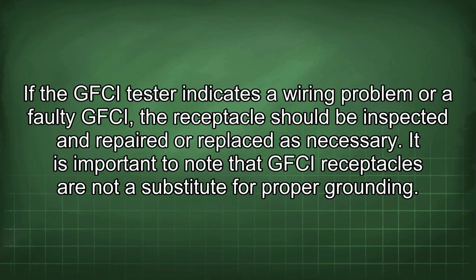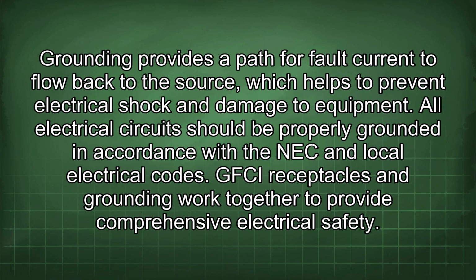If the GFCI tester indicates a wiring problem or a faulty GFCI, the receptacle should be inspected and repaired or replaced as necessary. It is important to note that GFCI receptacles are not a substitute for proper grounding. Grounding provides a path for fault current to flow back to the source, which helps to prevent electrical shock and damage to equipment. All electrical circuits should be properly grounded in accordance with the NEC and local electrical codes.